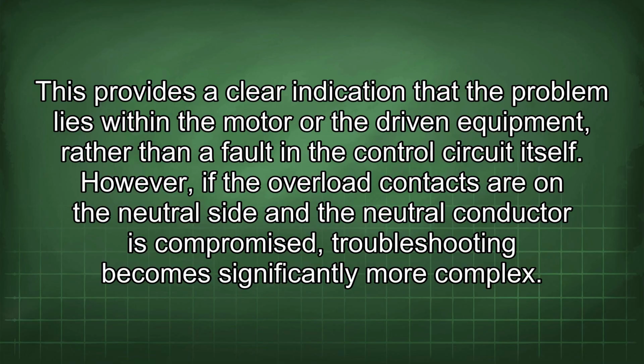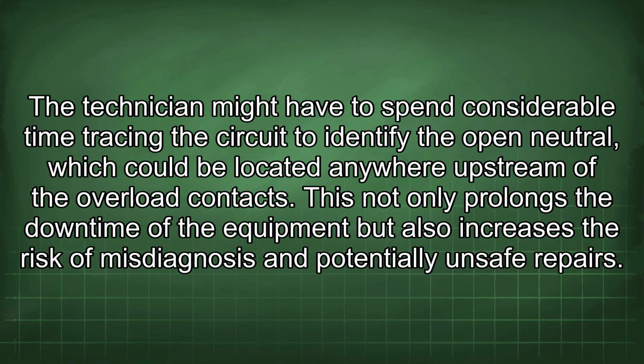However, if the overload contacts are on the neutral side and the neutral conductor is compromised, troubleshooting becomes significantly more complex. The technician might have to spend considerable time tracing the circuit to identify the open neutral, which could be located anywhere upstream of the overload contacts. This not only prolongs the downtime of the equipment, but also increases the risk of misdiagnosis and potentially unsafe repairs.